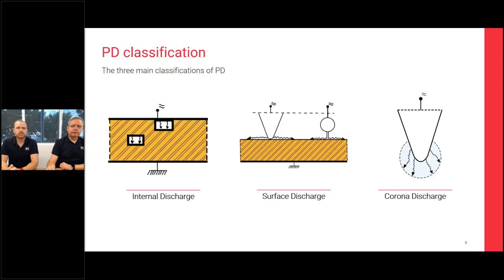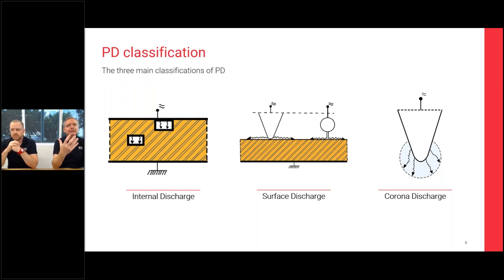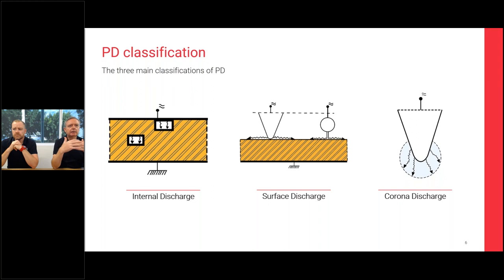A quick summary of the different types of partial discharge. The three main classifications are: internal discharge — happening deep inside solid insulation, the difficult ones you can't see, which cause disruptive failure with limited warning unless you carry out measurements. Second is surface tracking — occurring on the outside of insulation, manifesting differently: internal discharge is a big burst of electromagnetic activity, while surface discharge involves smaller sparks and tracking across insulation. These are the two main types we look for to prevent failure.